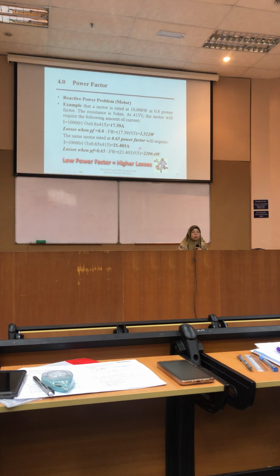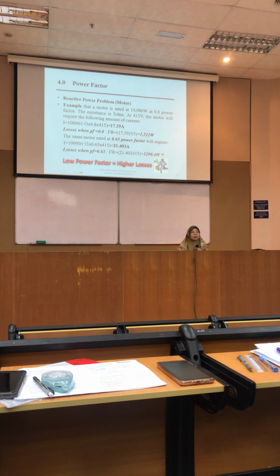When you have a power factor of 0.8, the losses are 1,500 watts. At a power factor of 0.65, can you imagine what the losses are? They go from about 1,500 watts to 2,200 watts when the power factor is below 0.8.